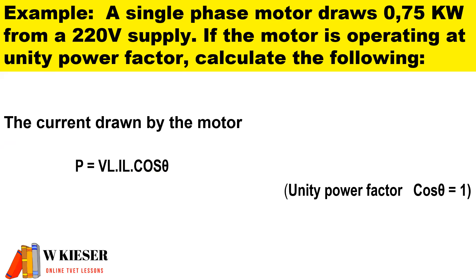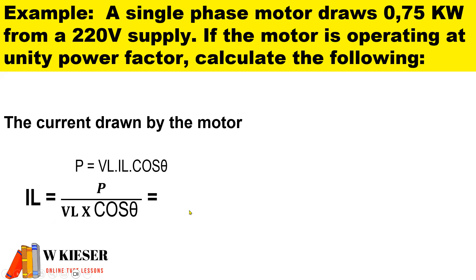To calculate the current drawn by the motor, just a reminder of the formula for true power: it is line voltage multiplied by line current multiplied by power factor. If we have unity power factor cos theta is equal to 1. So to calculate the line current is the power of 750 watts divided by 220 volts and the power factor of 1 and we get 3.409 amps.